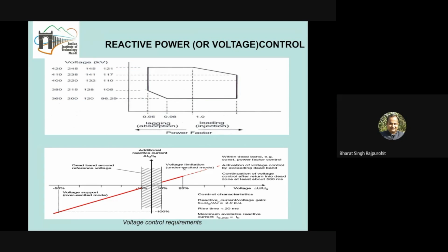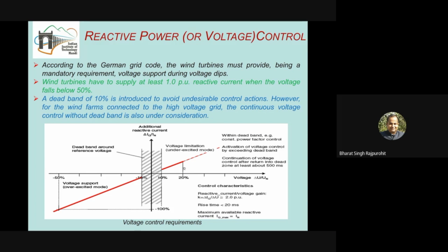But if you remember, reactive power absorption is possible for synchronous-machine-based wind turbines. The machines are able to absorb reactive power, and they are even able to generate reactive power. But what about the doubly fed induction generator system? It is not possible for the DFIG by itself to generate reactive power. It just absorbs reactive power, as it is an induction machine. But by utilizing the rotor side power electronic converter, it is also possible to generate as well as absorb reactive power. So overall, a doubly fed induction generator with power electronic equipment can both generate and absorb reactive power, which we are going to discuss in more detail.